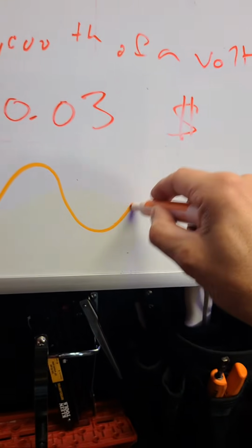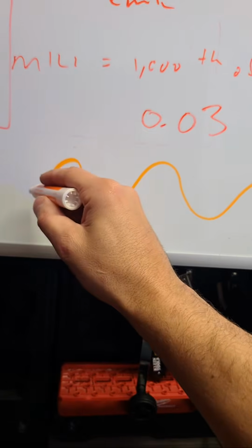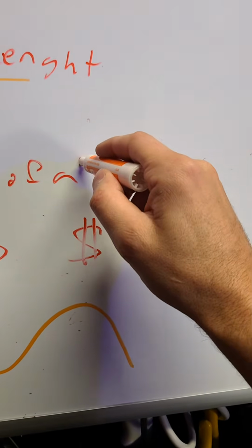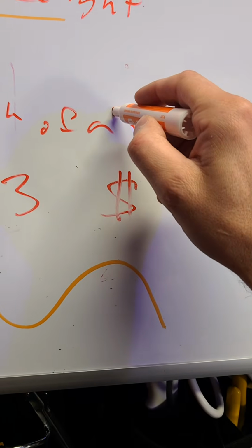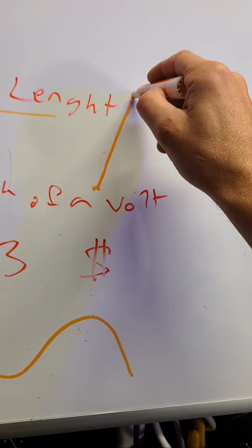Is inrush different from max amp setting? Yes. Current inrush is captured in the middle of a sine wave. So as your AC current is going like this, 60 hertz, 60 times a second, you've got 60 cycles in a second going. Only for a couple of cycles is that current very high. So when you have inrush current, it's kind of like being in first gear in your car, where it uses a lot of power and your RPMs go up really high.